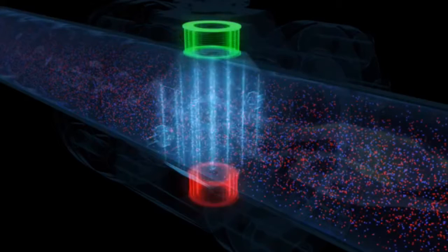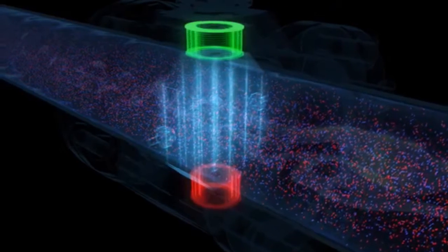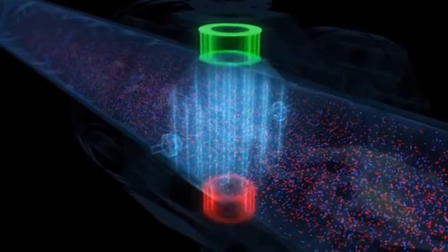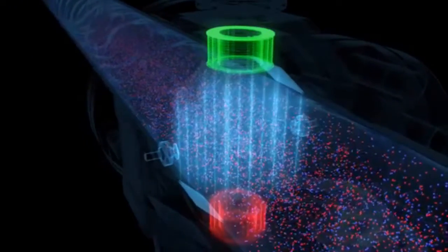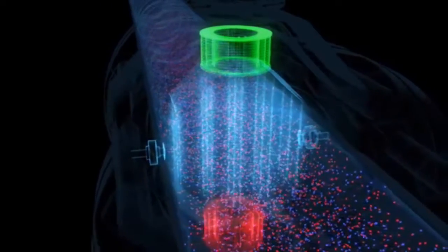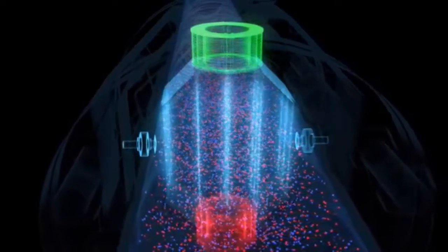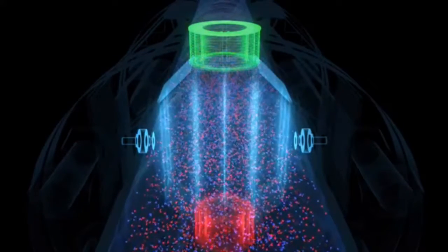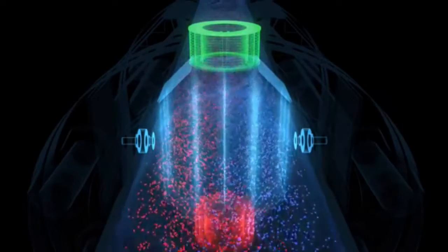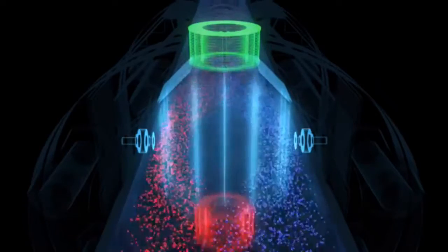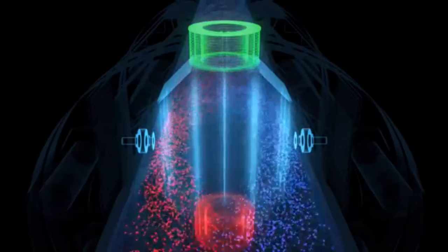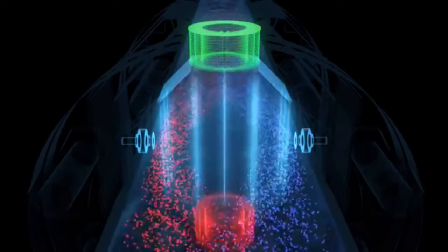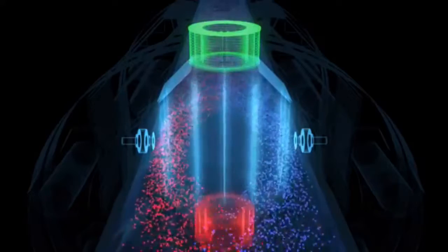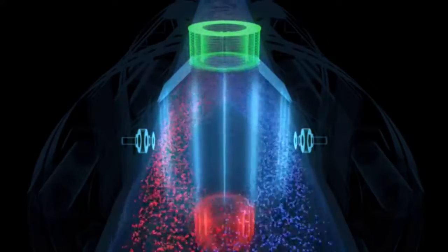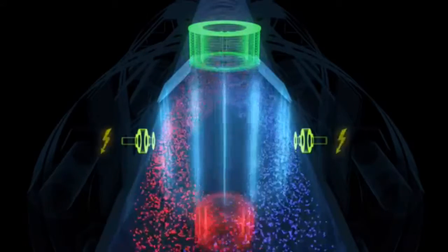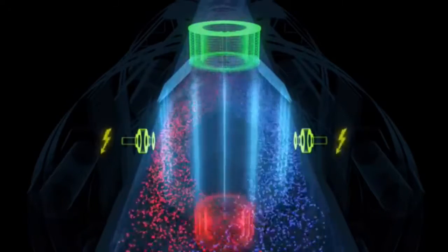electrodes. The electrically charged particles of the conductive liquid are evenly distributed, shown here in water, with red and blue particles. As soon as the liquid starts to flow in the measuring tube, the magnetic field applies a force to the charged particles. As a result, the positively and negatively charged particles in the liquid are separated and collect on the opposite sides of the tube wall. Now an electrical voltage forms, which is detected and measured by the two electrodes. This voltage is directly proportional to the flow velocity in the pipeline, and together with the known tube cross-section, the flow volume can now be calculated.